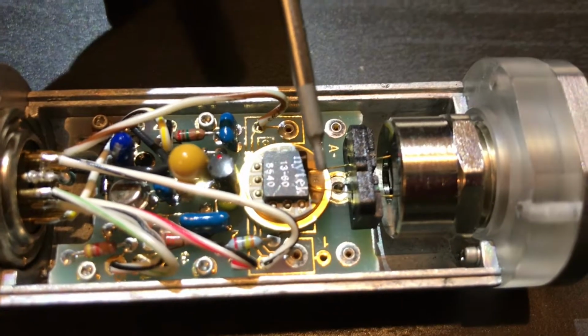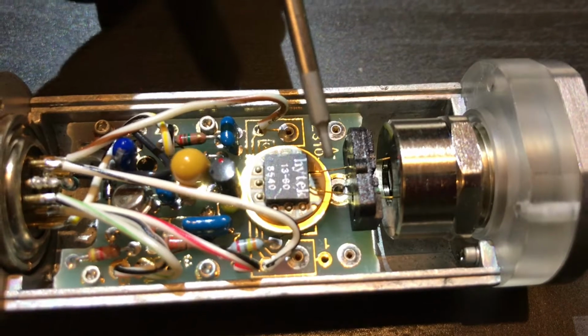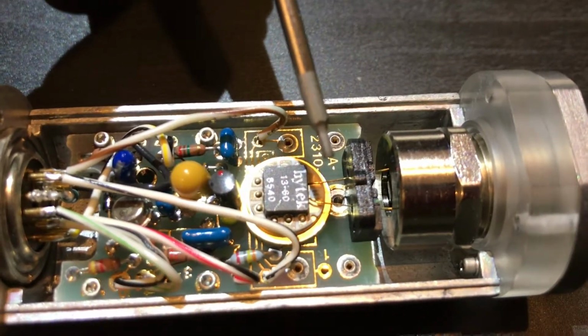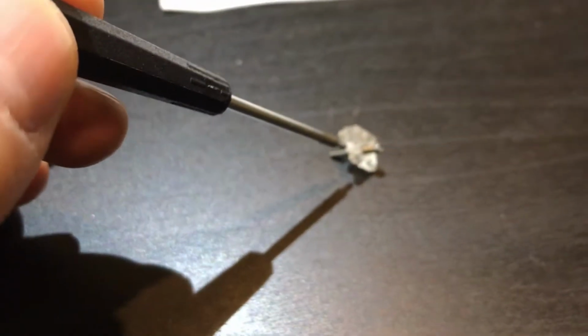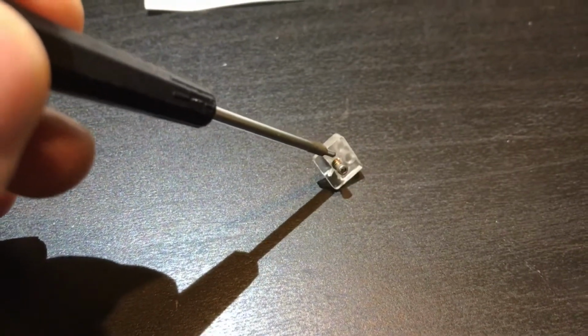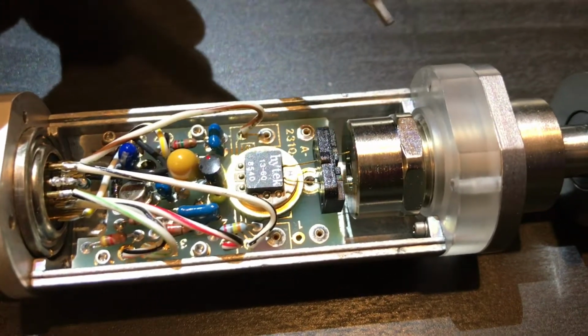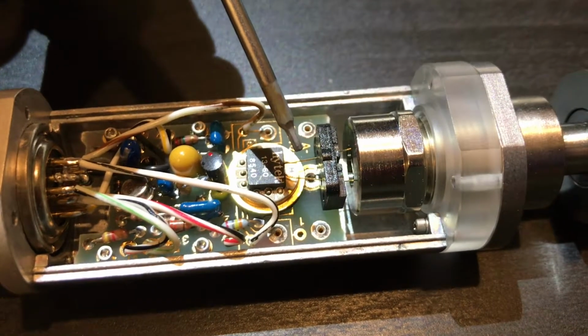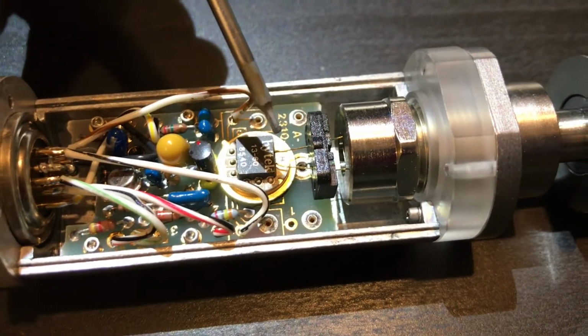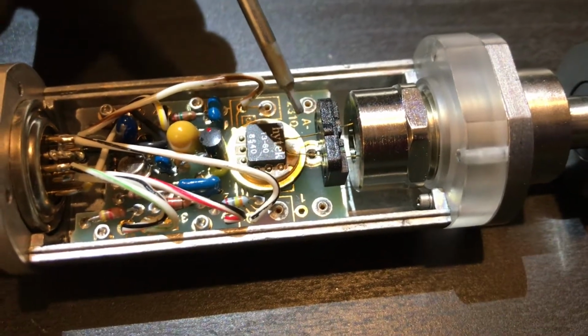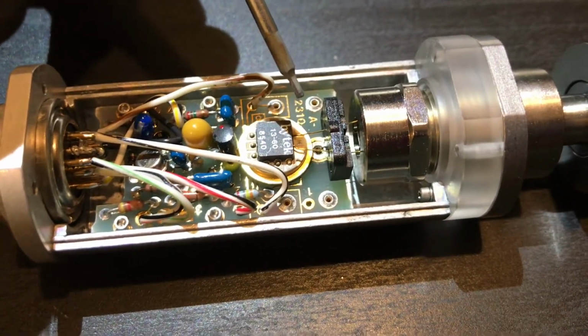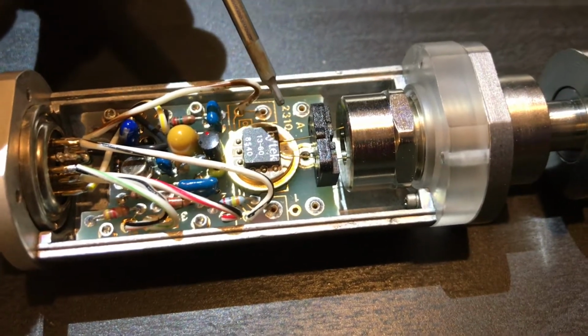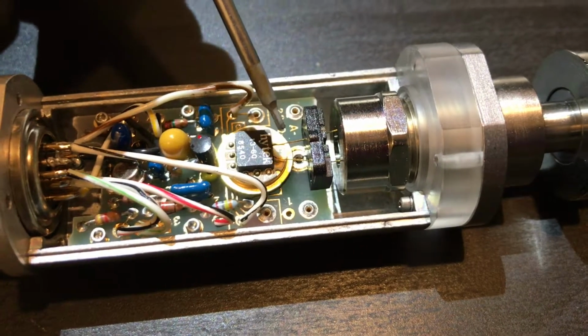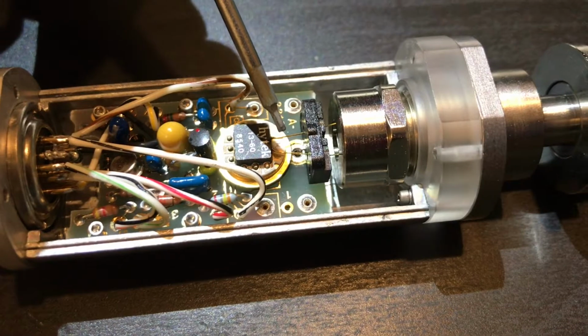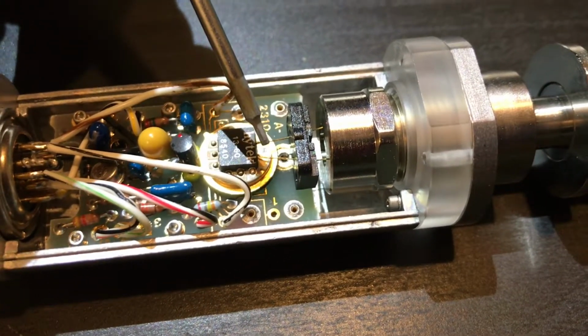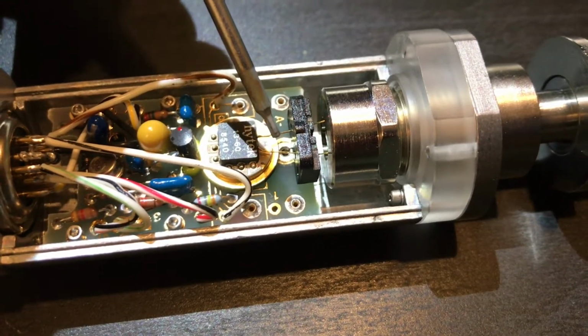Now the manual talks about when you disassemble this, there's two things you've got to be careful of. One, when you reassemble it, don't screw this clamp down too tight, because they're worried about cracking the clamp or causing a bad connection. And two, that you absolutely do not touch these gold leads with your bare hands, because your skin and body oils will get on there and they will affect the performance of the power sensor. So off camera, I'm going to look at this under my microscope and get a good look at the pads and the leads, and then I'm going to clean this with some alcohol. Once I get it cleaned, I'll bring it back and we'll see if it's working better.